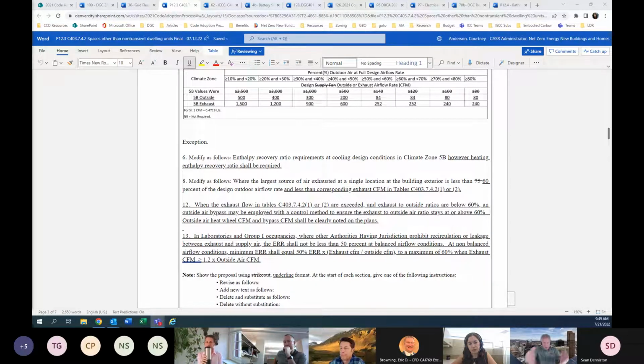that all this complexity does 2 things. One, that's imbalanced right there. You'll never get 60% when you've only got 1,500 CFM, and we need to pressurize the building, right? So I can't just bring outside air, or I shouldn't, a good designer shouldn't just take building air and throw it away because we need it for pressurization.